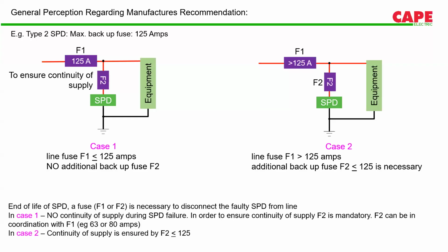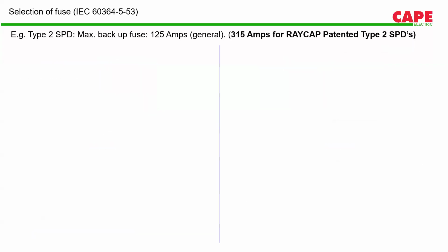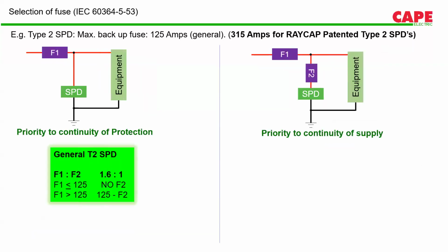So if we need priority to continuity of supply, we need to use a backup fuse irrespective of the incomer rating. So this is what I was explaining, priority to continuity of protection and priority to continuity of supply. Priority to continuity of supply is required in applications like data centers or some process industries where they always want their plant or the conveyor belt or any equipment to run every time. So they don't want any disconnection in supply. In these places we have to ensure that we are using a backup fuse F2 irrespective of the incomer rating.